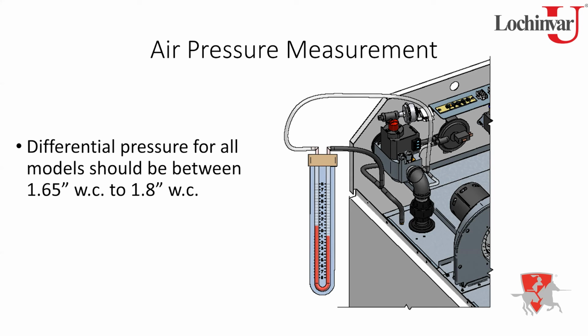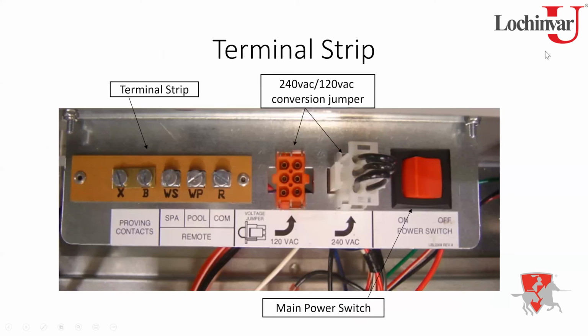Yeah, when people see that low air switch open fault, there's a lot of assumptions they make. A lot of times we'll just assume it's a bad switch. Oh yeah, that's the biggest one all the time. And it's typically not a switch issue. So don't replace a switch until you actually measure the pressures and see what you're dealing with. Yep, absolutely. Now we start looking at the wiring.